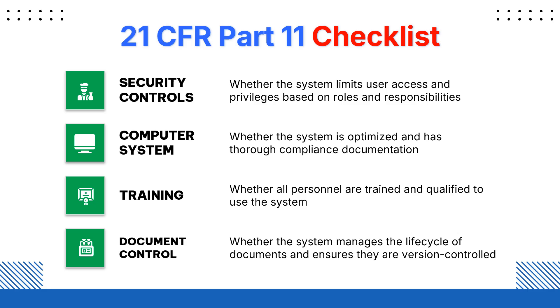So these eight particular requirements — validation, audit trail, electronic signature, record copies and retention, security control, computer system compliance, training, and document control — are the requirements of 21 CFR Part 11. Whenever you check compliance for 21 CFR Part 11 for electronic documentation and signatures, you need to verify all these parameters to ensure that the system is compliant.